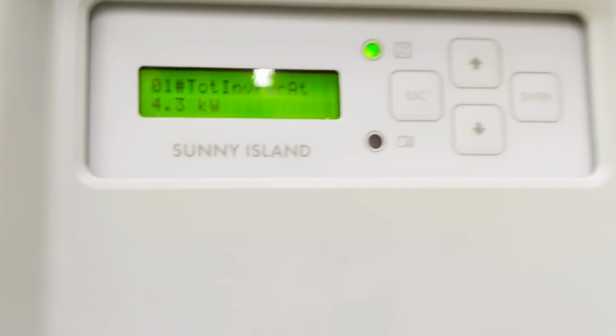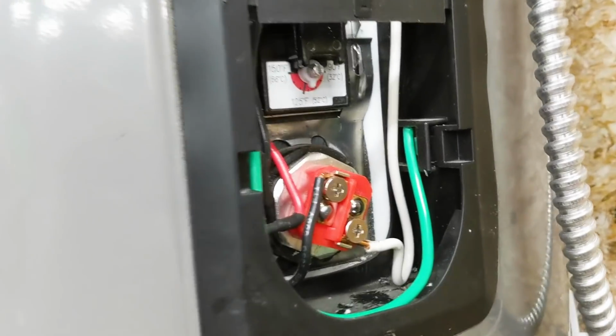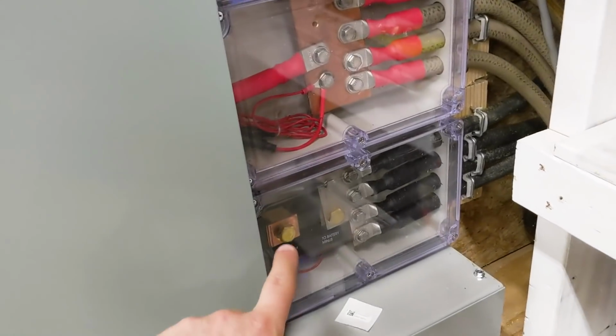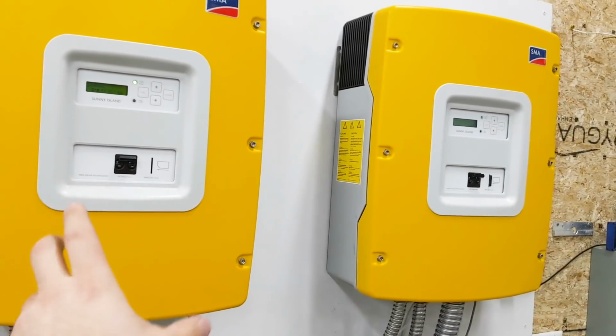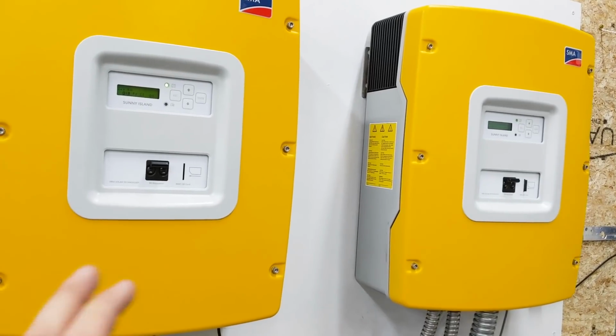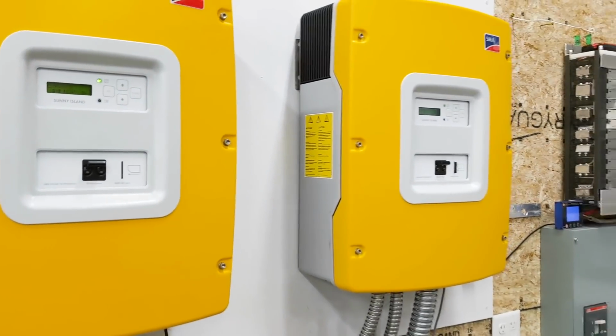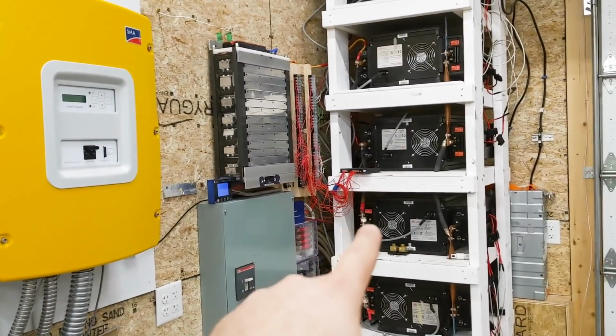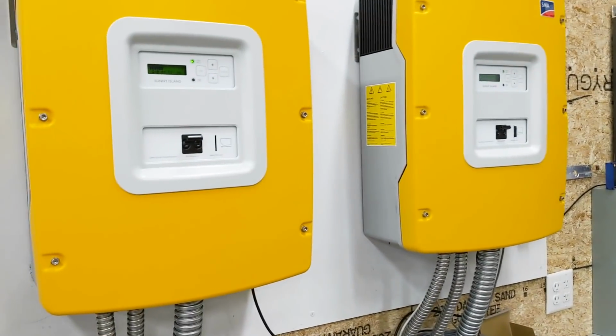4.3 kilowatts, and this water heater is kicking on, this one right here. I just checked the shunt, and it says 4,600 watts is being discharged through the shunt, and this says 4.3 kilowatts. That tells me that these two inverters are using 300 watts right now in the conversion process of taking the DC and making the AC.